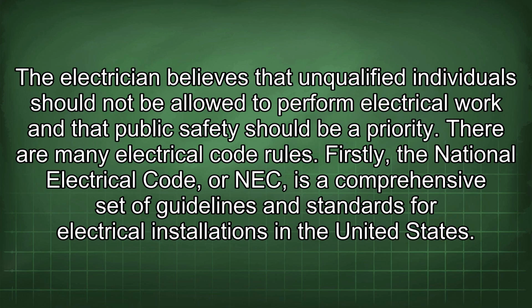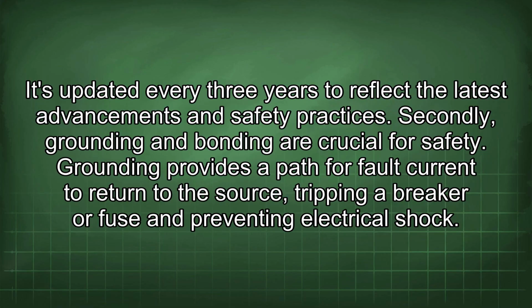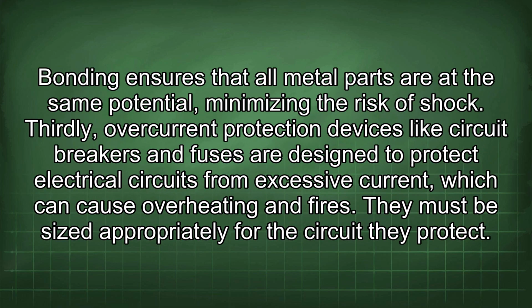Firstly, the National Electrical Code, or NEC, is a comprehensive set of guidelines and standards for electrical installations in the United States. It's updated every 3 years to reflect the latest advancements and safety practices. Secondly, grounding and bonding are crucial for safety. Grounding provides a path for fault current to return to the source, tripping a breaker or fuse and preventing electrical shock. Bonding ensures that all metal parts are at the same potential, minimizing the risk of shock.